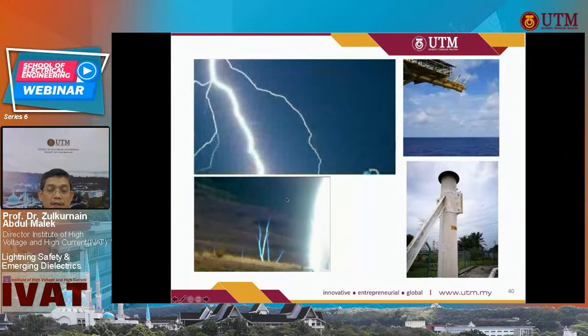Finally, what happens is, when the leaders start coming down, they bring a very large electric field, which can actually induce upward leaders from the grounded objects. And this doesn't spare the so-called vent stack at the chemical industry. These are cold vent stacks where waste gas comes out. More often than not, the waste gas is flammable, and it is not supposed to ignite. Therefore, if fire catches because of some sparking at the edges of the vent stack at the moment we release the gas, this will be a cause for concern to the owner of the unit.